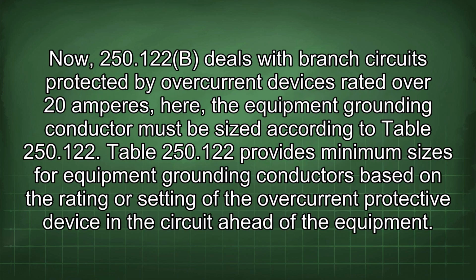Now, 250.122(B) deals with branch circuits protected by overcurrent devices rated over 20 amperes. Here, the equipment grounding conductor must be sized according to Table 250.122. Table 250.122 provides minimum sizes for equipment grounding conductors based on the rating or setting of the overcurrent protective device in the circuit ahead of the equipment.